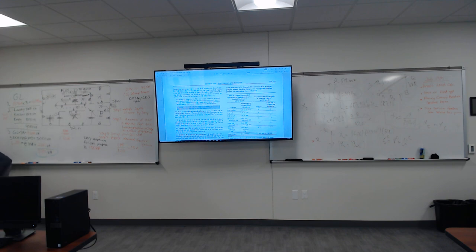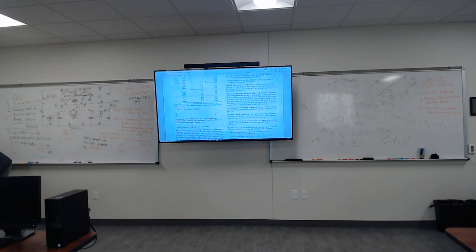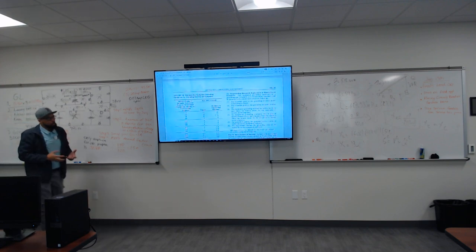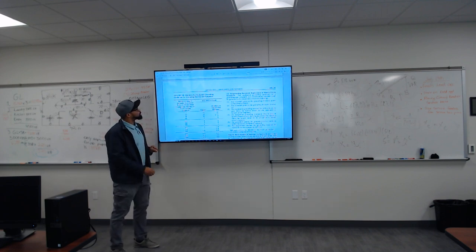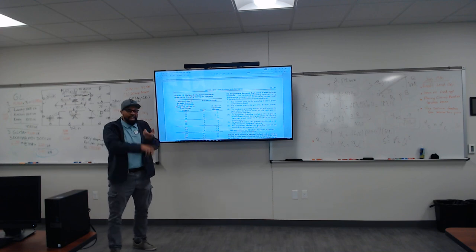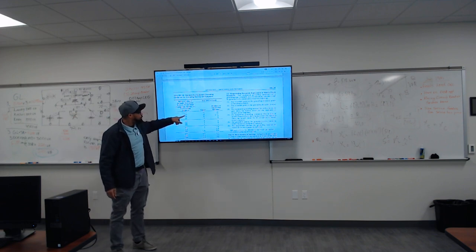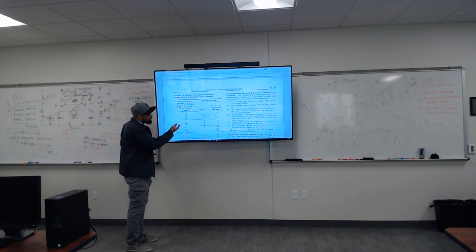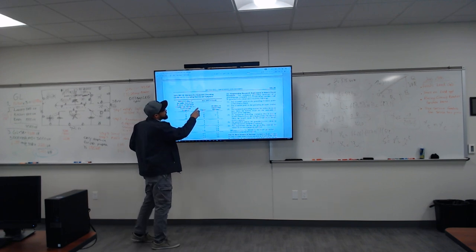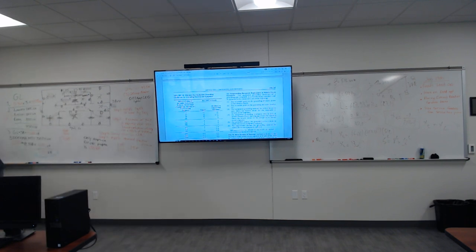All right, now, let me show you another table. This is another one that we highly use as electrical engineers or electrical technicians or electricians. Minimum size equipment grounding conductors for grounding raceways and equipment. Equipment is your AC unit, motors, stuff that is equipment, all right? And then you go off of the size of the circuit breaker. For example, like our heater. When we figure out the size of the circuit breaker for our heater, then we figure out the size of the grounding conductor. I'll get to that later though. So there's three tables that we do. Let me go figure out the next question that we've got to figure out.